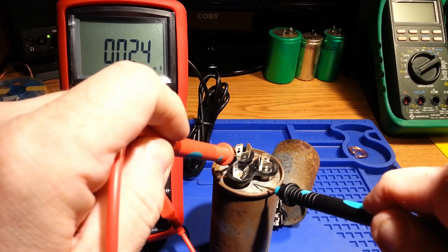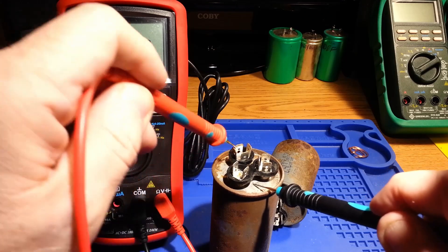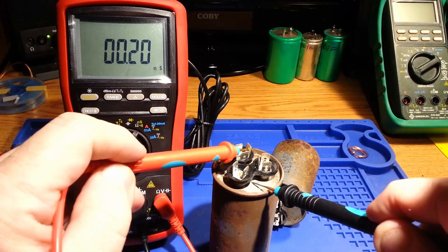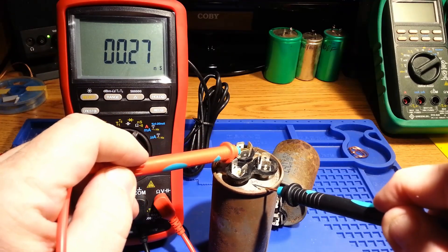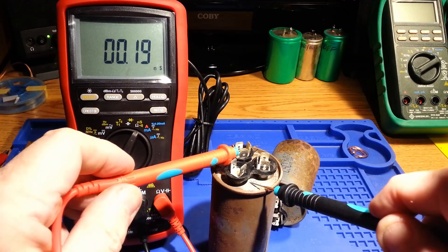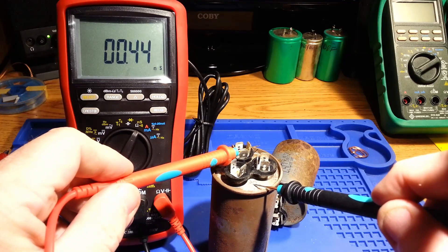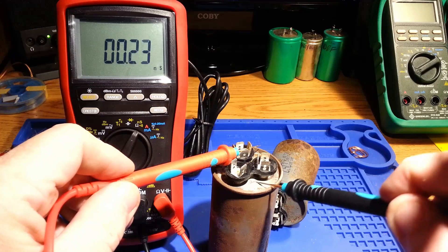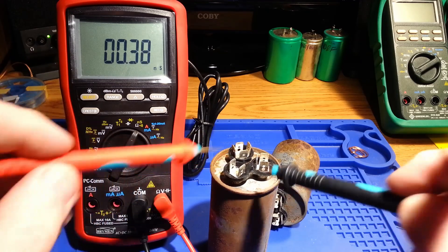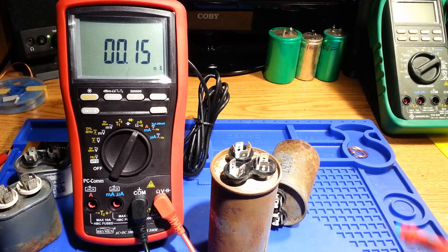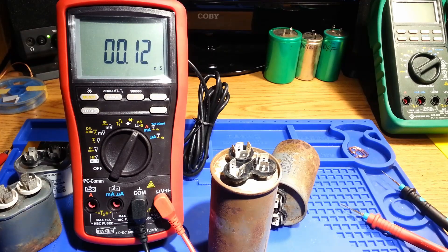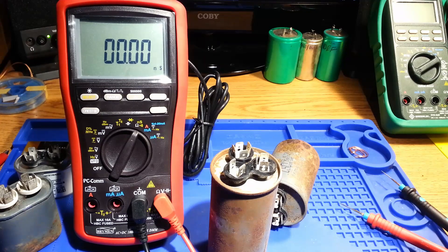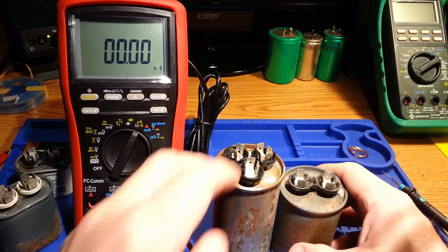this one is measuring out about the same. It's having something going on with the common lead on this one. So it's close to the value of a new case or just starting to get into the infancy of having an internal breakdown between the case and the capacitors.